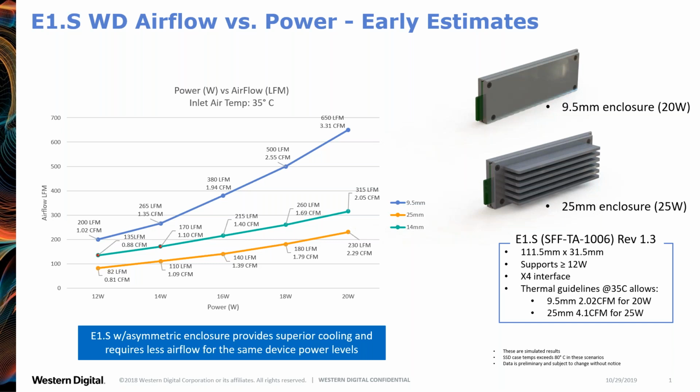Is this through-channel airflow or approach? This is approach. As was discussed before, approach speed, pressure head, and local speed are all interrelated, so requesting one is going to affect all of the others. As a system-level designer, or between system-level design and device-level design, it's always good to have good communication between all three of those variables. And this is just for a single SSD? This actually considers multiple SSDs in line: a center SSD with adjacents on either side in a stack of 5.